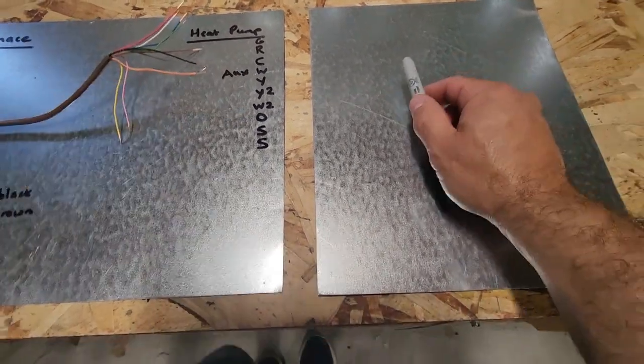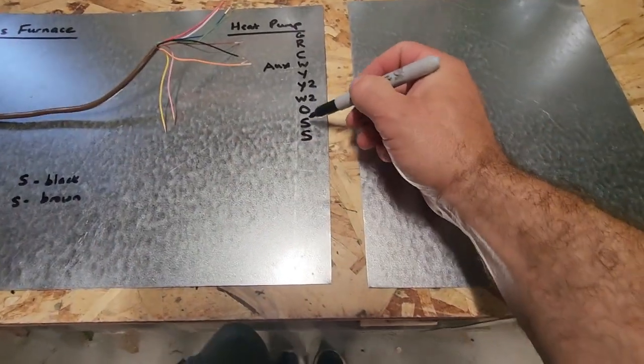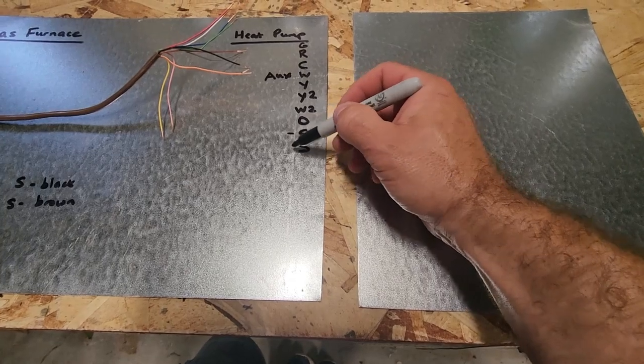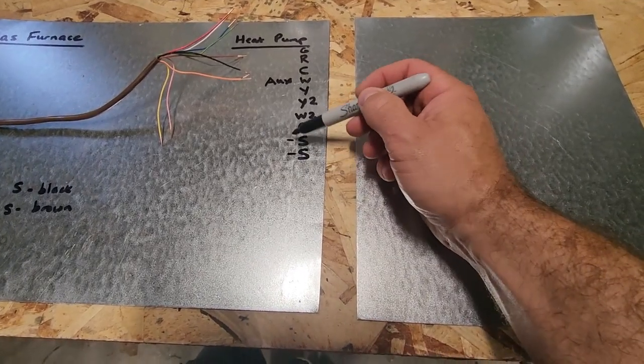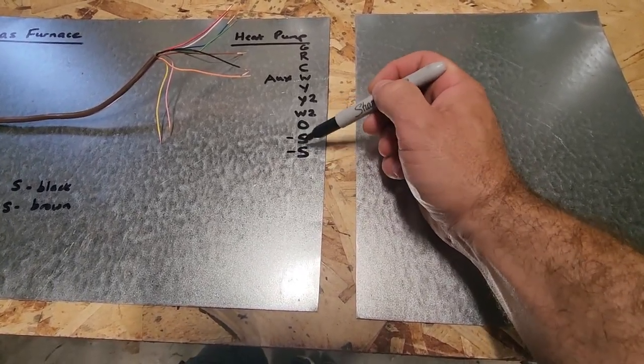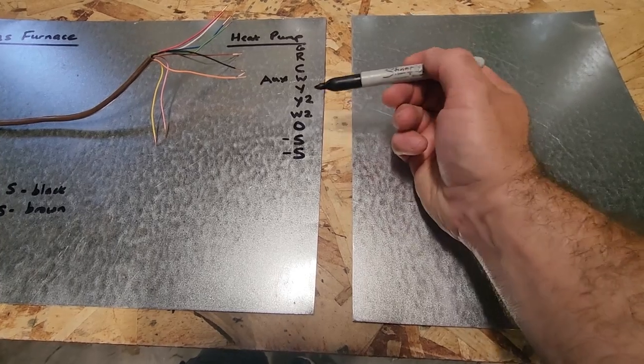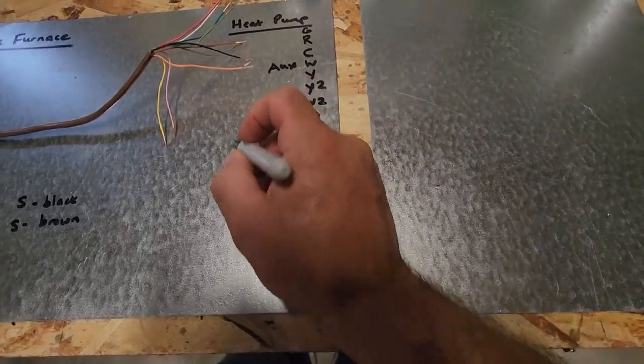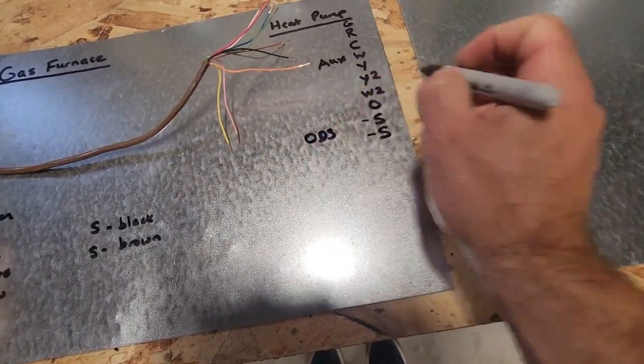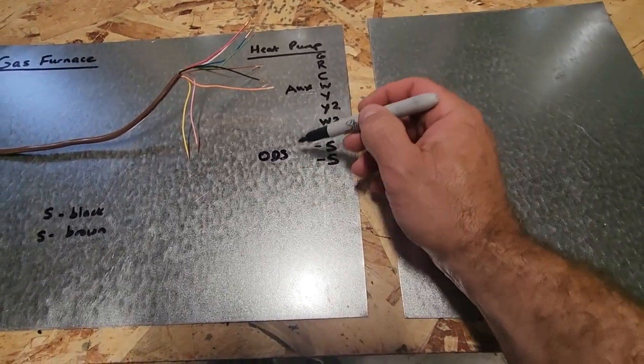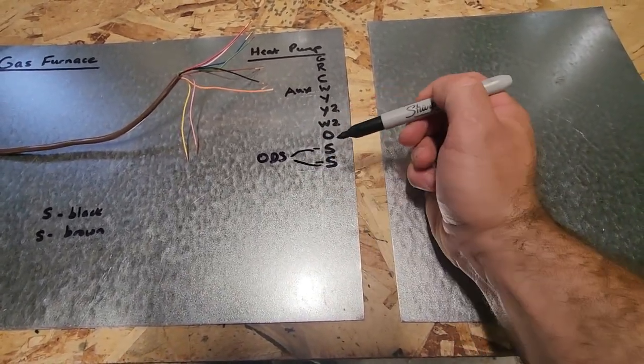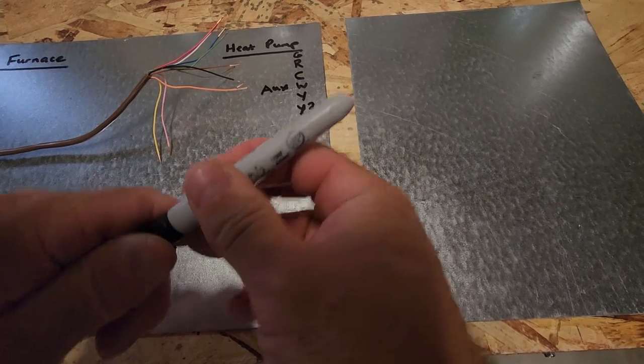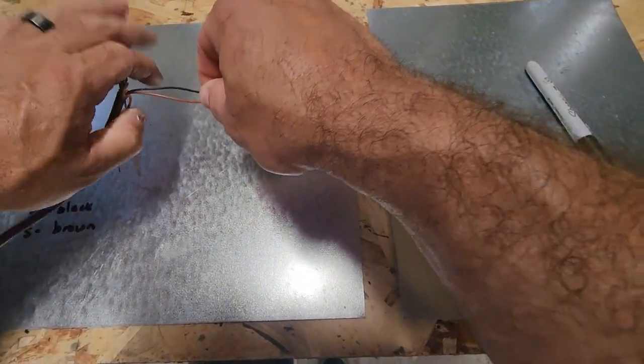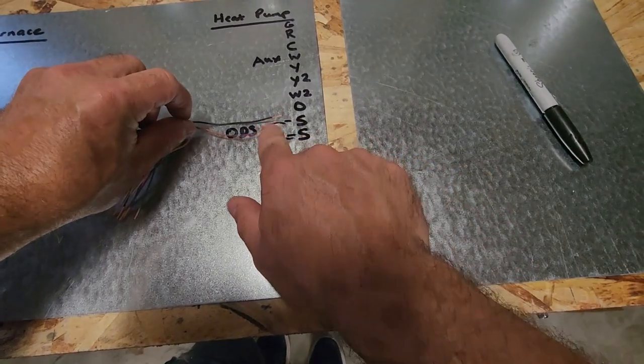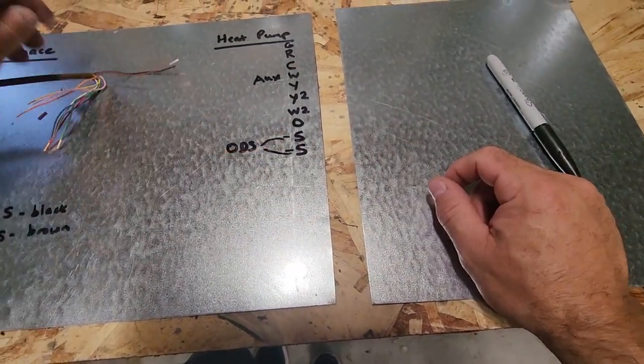And then lastly, you have usually a couple of S terminals on your thermostat for a heat pump if you have a heat pump that does it. Now, some of the Wi-Fi ones don't because they do it via the internet. This is for an outdoor sensor, okay? Call it an ODS. So you'll have a 2-wire sensor that'll go outside and it'll wire directly. Now that's why I leave the black and the brown left. It's the only thing that's not being used here, okay? I like to use those 2 every time, then I don't screw it up.